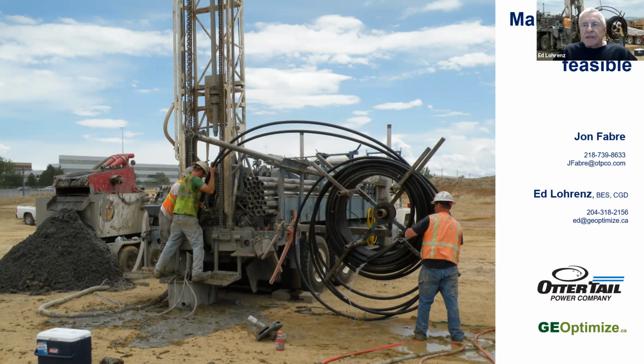One thing that we've done in the past is to use existing energy models of existing buildings that are similar to the building that our client is looking at. So for example, if they've got an apartment building in Albany, New York, and we've done a similar building in Toronto, we would take that same original energy model, might make some modifications to the size and to the window to wall ratio and things like that, do that fairly quickly without spending a lot of time on it, and run that energy model using Albany weather data and see what happens. Then do a review of the geology of that area and look at the land area. We can do that fairly quickly by possibly talking to a few drilling contractors or looking at water well databases or whatever. And in about a day or two, we can get a fairly reasonably solid number on that.